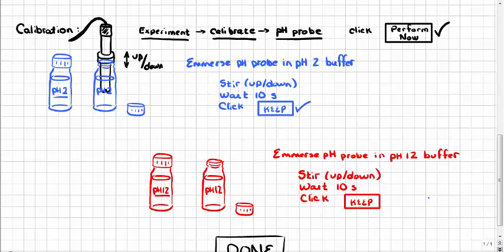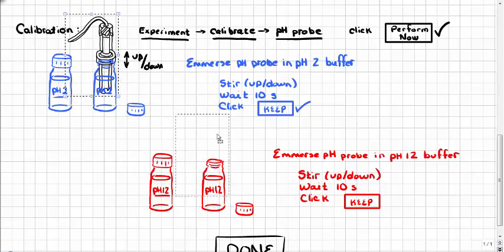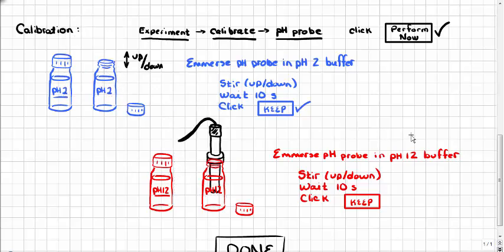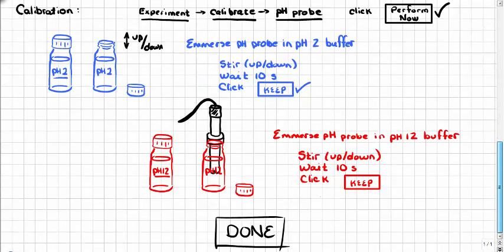Now, the next thing that we have to do is complete the 2-point calibration by taking the pH probe and moving it to the pH 12 buffer solution. So we immerse it directly into the buffer solution with the pH 12, and then again we do the same sort of thing. We stir using an up and down motion to make sure that there's fresh solution passing over the tip of the pH probe. After waiting about 10 seconds or so, and again remember that the large display in the background is not going to be active during this time, you will click Keep. And then finally, it's necessary to finish the calibration by clicking the Done button.